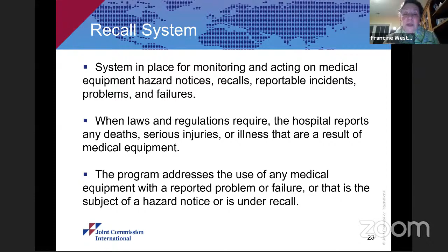When your laws and regulations require that you report any of these deaths, serious injuries, or illnesses that are the result of medical equipment, make sure that you have a process in place for reporting that appropriately. And make sure that your program addresses the use of any medical equipment with a reported problem or a failure that is subjected to a hazard notice or is under recall by the manufacturer. Please keep in mind that when you're looking at your medical equipment, to include your point of care testing, how is that being calibrated, for example, your preventive maintenance program evaluation and effectiveness, work order management system.